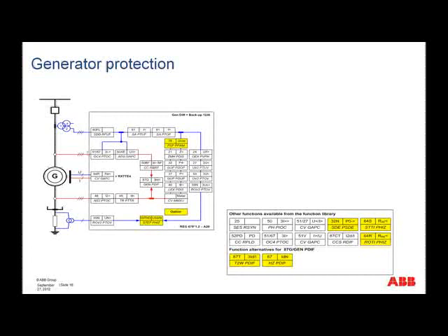And then, of course, we have a number of functions which would measure current and voltage. And here we are talking about things like the pole slip protection, under impedance, over or under power, loss of excitation. Then we have voltage measuring functions, and here we look at functions such as over excitation, over or under voltage, residual over voltage, and then also functions like over and under frequency.